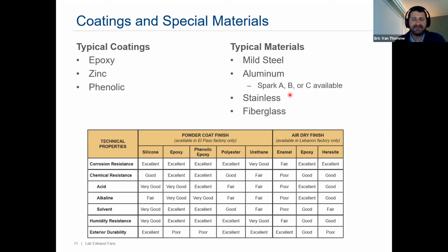We also can build fans out of stainless steel. Some manufacturers get into fiberglass. We do not, but that is also a typical material for laboratory exhaust fans. Our typical coating is a zinc-rich epoxy primer with a UV top coat. All of these fans are typically mounted outdoors, so you're going to have some sort of UV protection included as part of the coating.